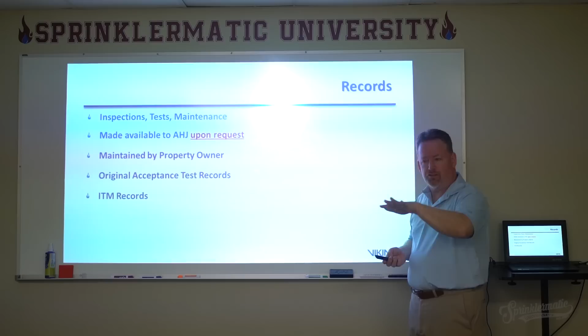The records should show what procedures, all of these records, these forms that are submitted not by the authority, but by the contractor, by the inspection technician. All of these records should show the procedure that was performed. Was it an inspection? Was it a test? Was it maintenance? Who did it? What was the required frequency of this particular event? What were the results and the qualified contractor's information? If it was done by a licensed contractor, then who was it? And so all of that information is now required by NFPA 25 as far as information on the list for the record.